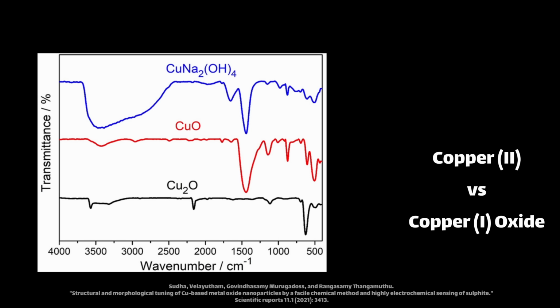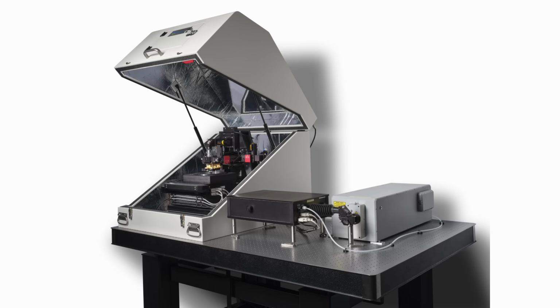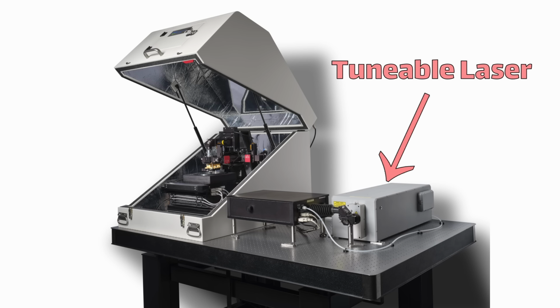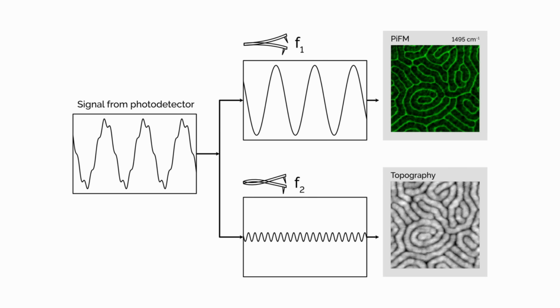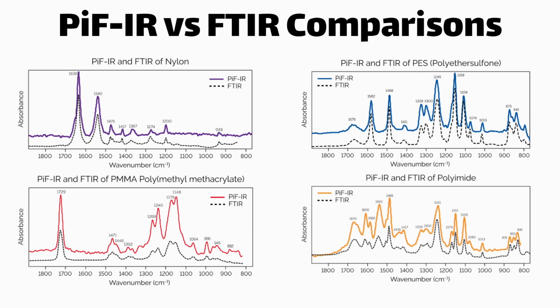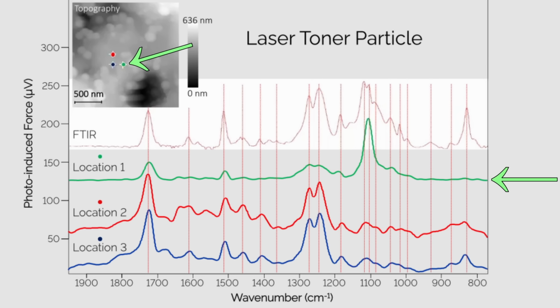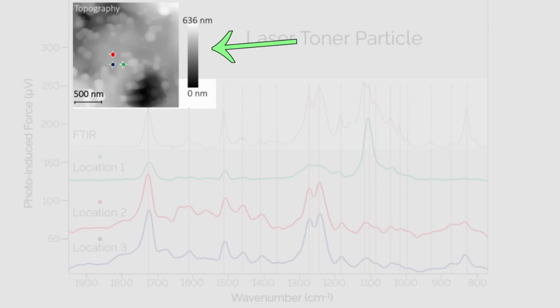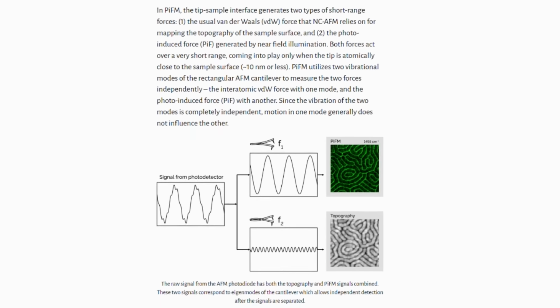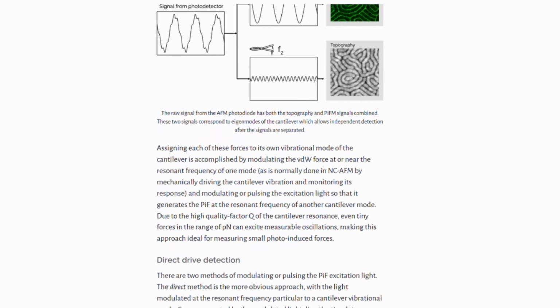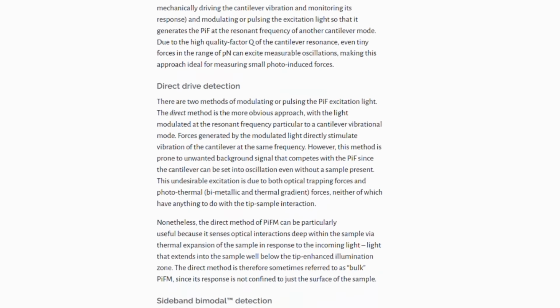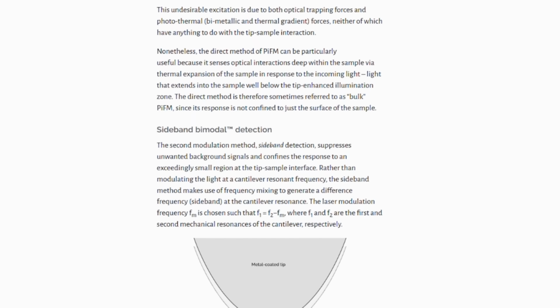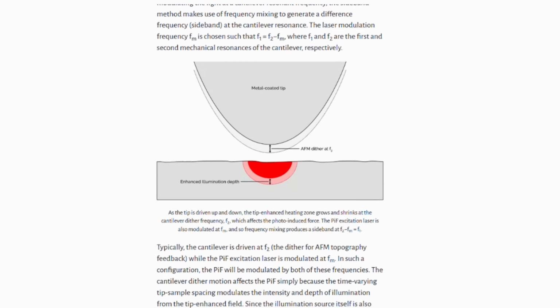So the Vista 200 works by scanning a tunable infrared laser across a wide range of frequencies, and then measuring the resulting photo-induced forces on the tip. The forces at different frequencies are then plotted to generate a traditional IR spectra. You get a chemical makeup like IR, but resolution like an AFM. And because it basically is an atomic force microscope, you also collect topographic data at the same time. The way it does both at the same time is by utilizing multiple resonant modes of the cantilever and modulating the frequency of the laser. It's a little too in the weeds to talk about here, but if you're interested in more details, I've got a link to a white paper describing how it works down below.